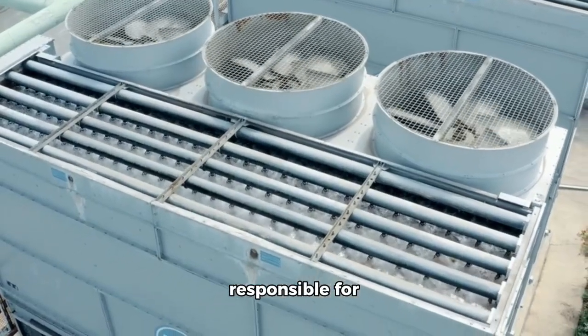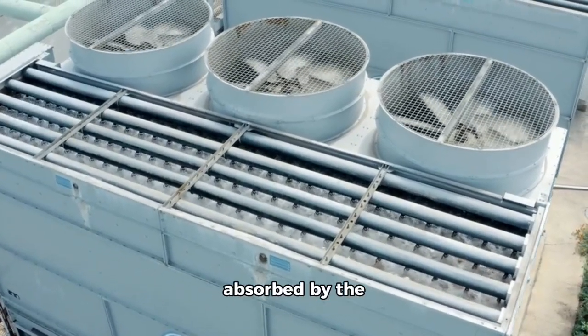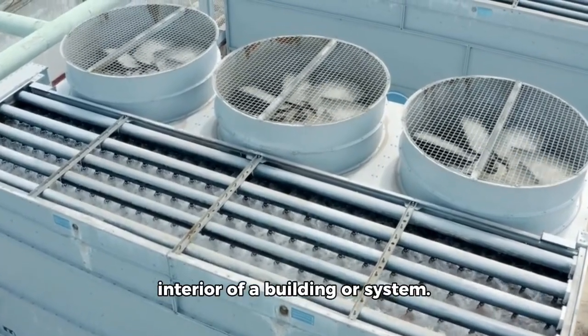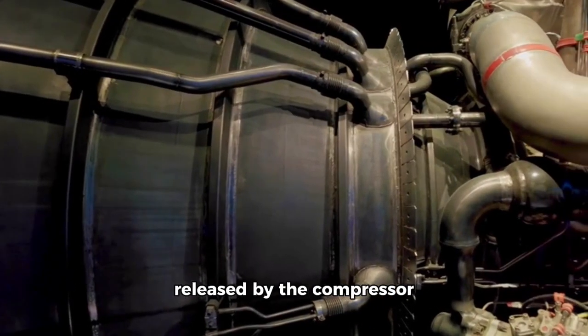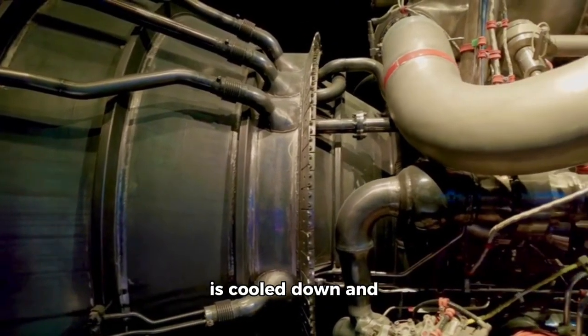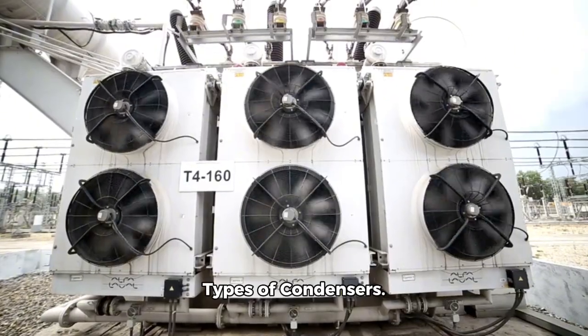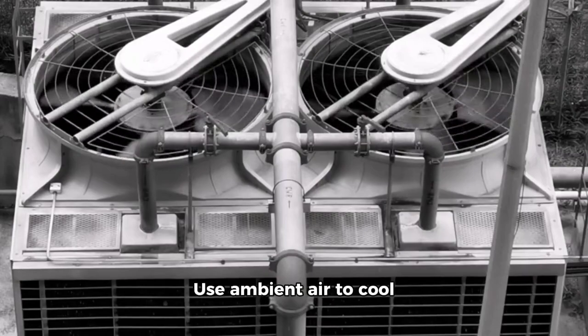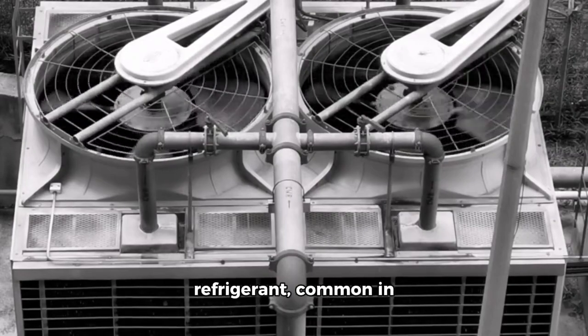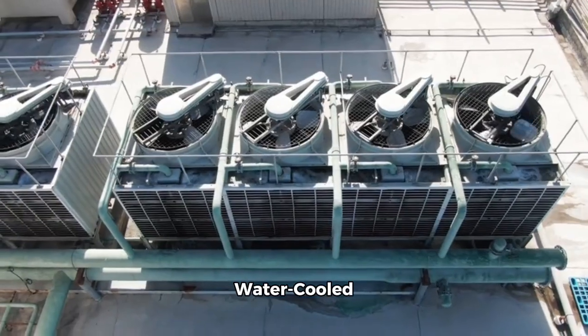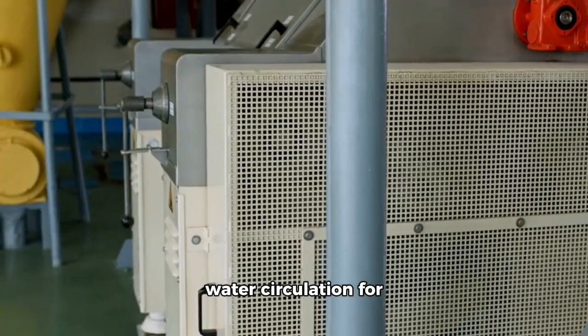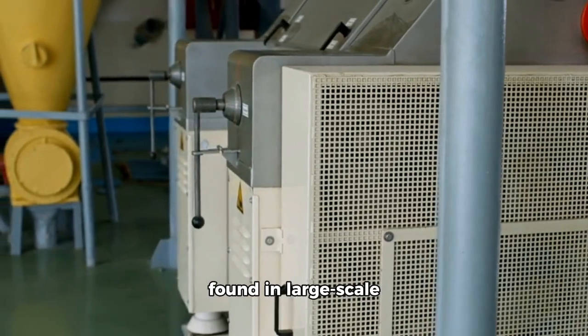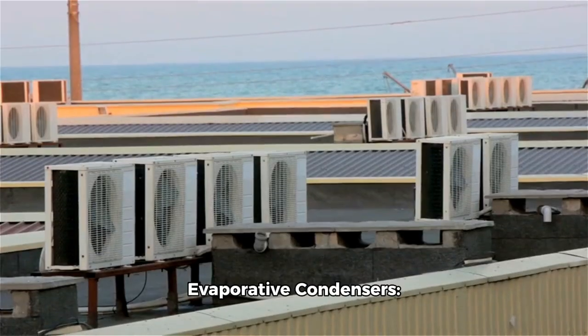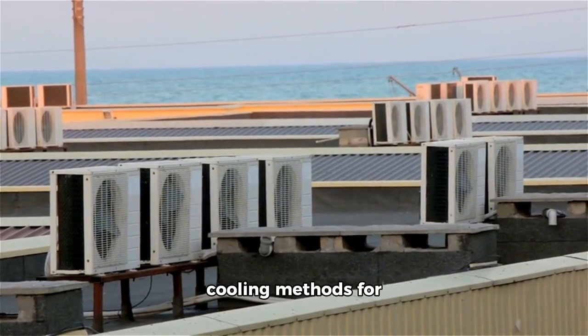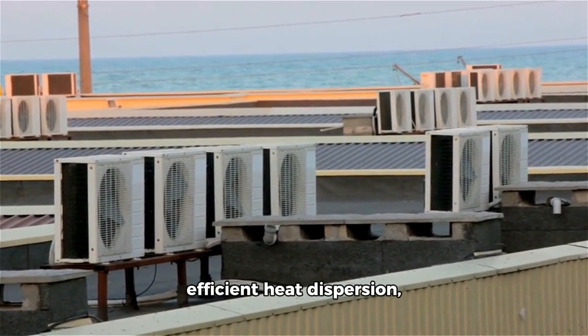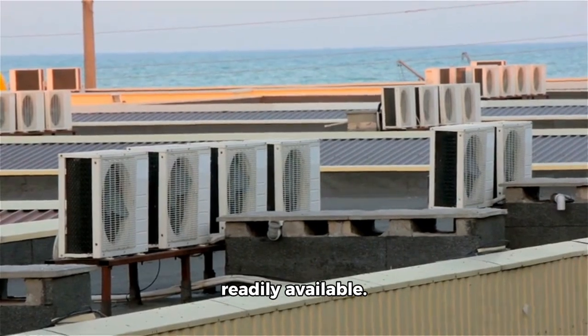Condensers. The condenser is responsible for expelling the heat absorbed by the refrigerant from the interior of a building or system. The high-pressure gas released by the compressor is cooled down and condensed into a liquid state. Types of condensers. Air-cooled condensers use ambient air to cool and condense the refrigerant, common in domestic appliances. Water-cooled condensers utilize water circulation for cooling, typically found in large-scale industrial applications. Evaporative condensers combine air and water cooling methods for efficient heat dispersion, often used where water is readily available.